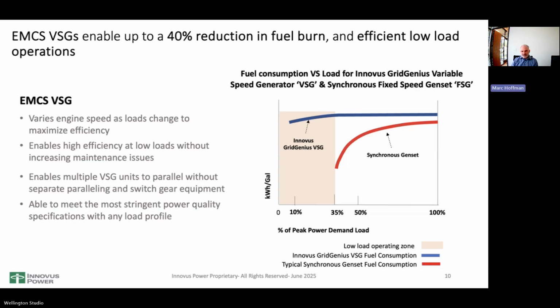With a variable speed generator, because we're allowing the engine to run up and down in speed, it stays efficient from very low loads, and we don't even start to see a slight degradation until somewhere around 20%. It's just because at some point the heat drops a little bit, but we can run all day and night at 10 or 20% versus a synchronous genset.